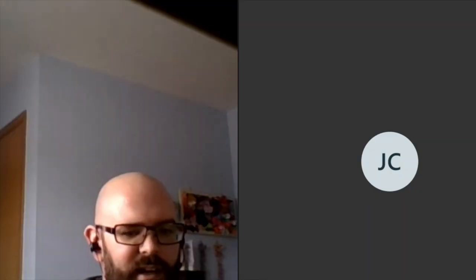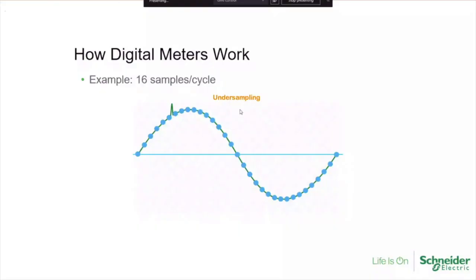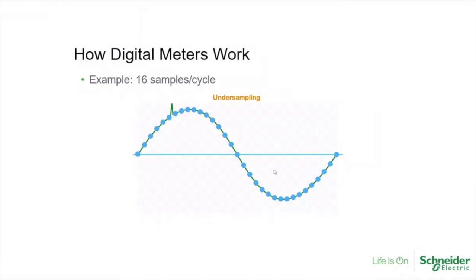But what this example illustrates is that if the peak, and the rising and falling, is in between your samples, the meter won't even notice it. It'll go completely undetected, or it'll get averaged out. So having a high sampling rate on your waveform capture is critical for transients, because otherwise you could wind up missing the event capture.